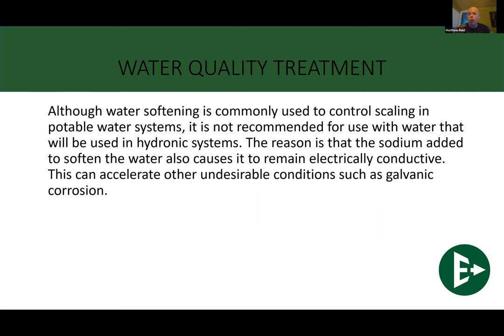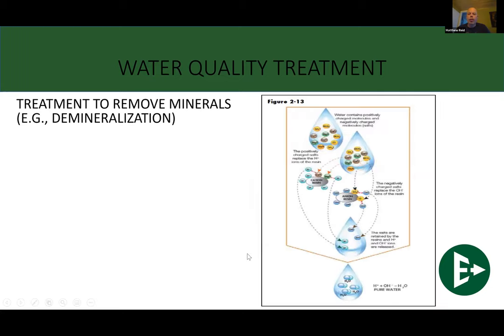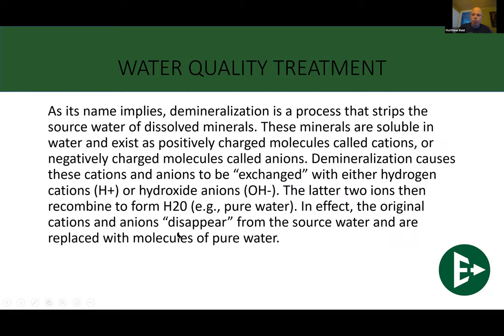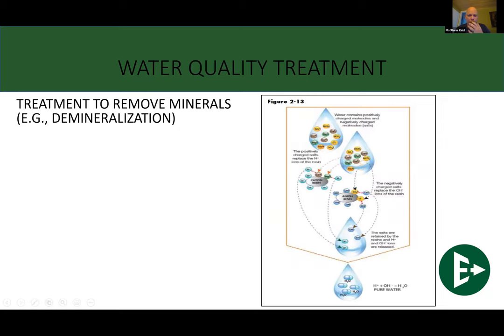So what other options do we got that's not going to create high sodium levels, which can accelerate our corrosion of the exterior and some interiors of the metal? We can move our thoughts now to demineralization. Demineralization, we can do either in existing systems, we can fill a system with it, but it's doing essentially the same thing as a water softener where we're doing an ion exchange.